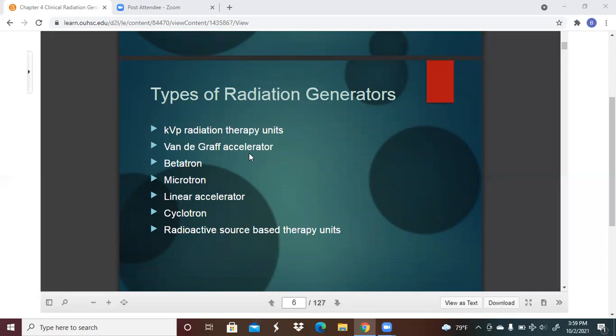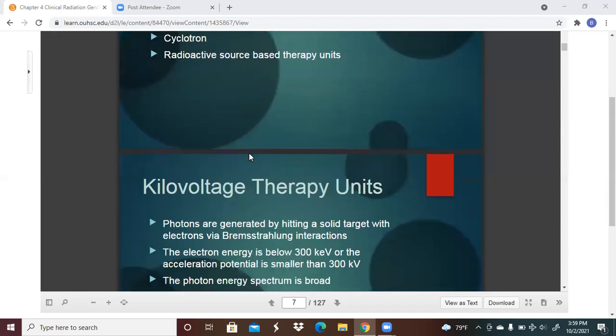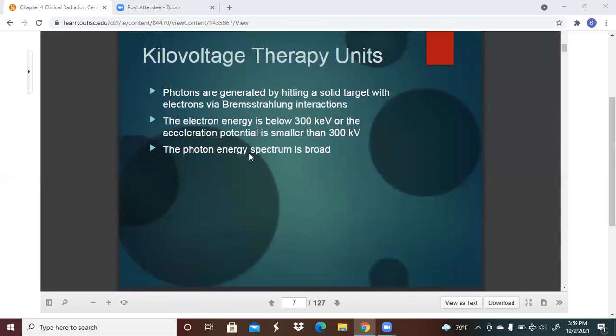So what type of radiation generators do we have? We have the kVp radiation therapy units, Van de Graaff accelerators, Betatrons, Microtrons, linear accelerators, Cyclotrons, and radioactive source-based therapy units. So, kilovoltage therapy units. Photons are generated by hitting a solid target with electrons via Bremsstrahlung interactions, which we covered in chapter 3. The electron energy is below 300 keV, or the acceleration potential is smaller than 300 kV. So the photon energy spectrum is in fact pretty broad.